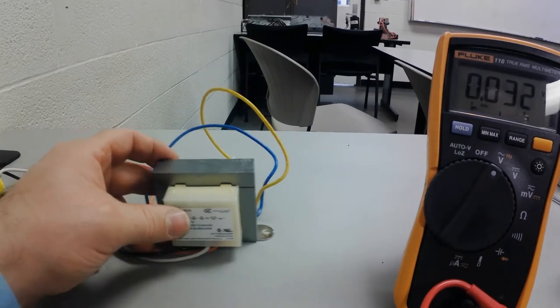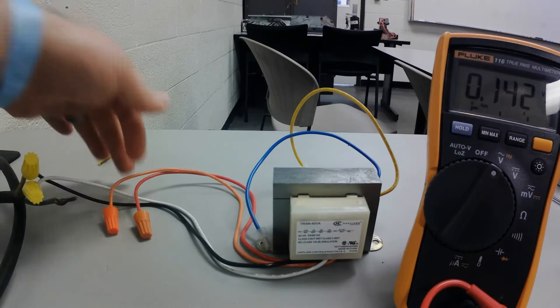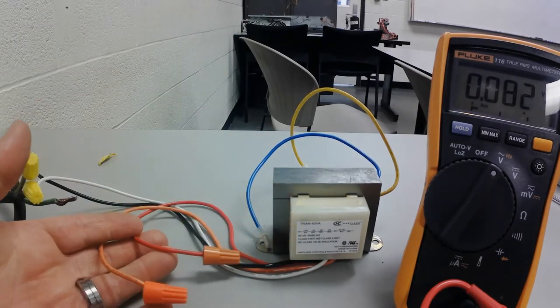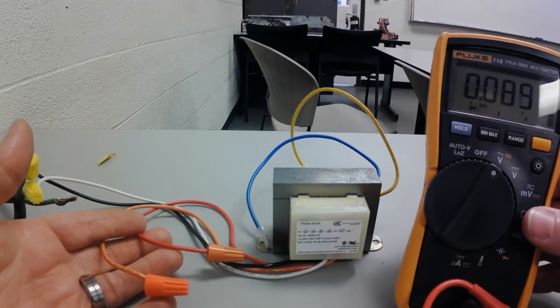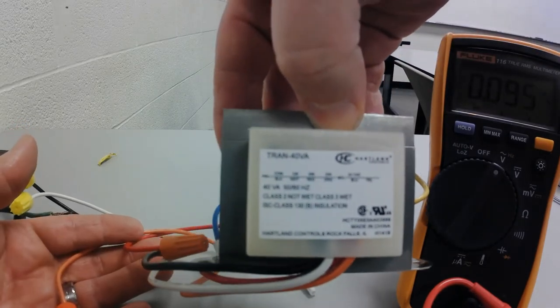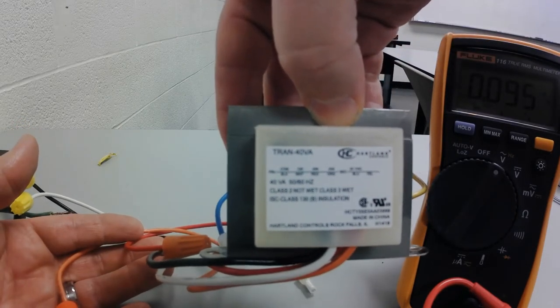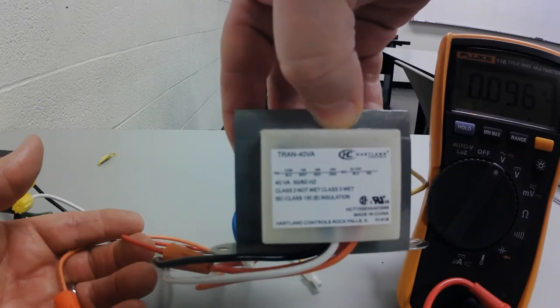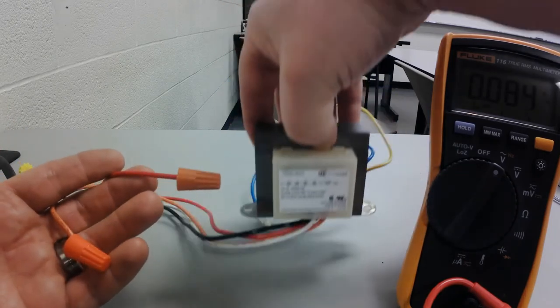So with this one, what I've got here is the red and the orange wire. Now, according to the manufacturer's information, I'm going to use the red and the black if I have a 208 power source, and I'm going to use the orange and the black if I have a 240 power source.